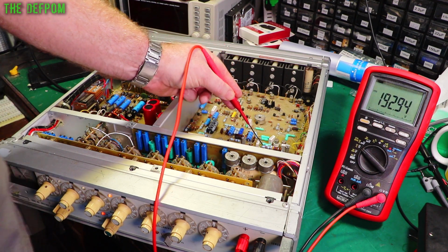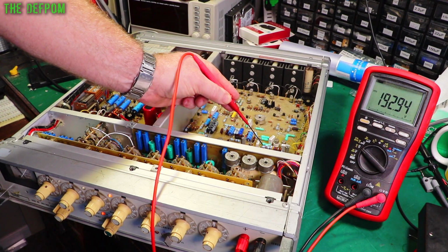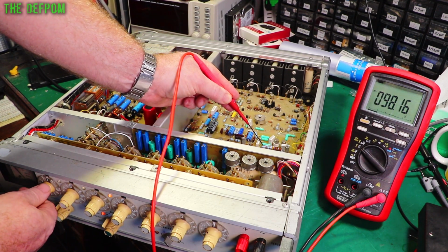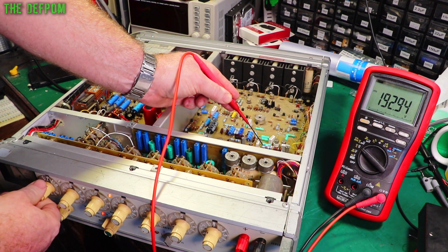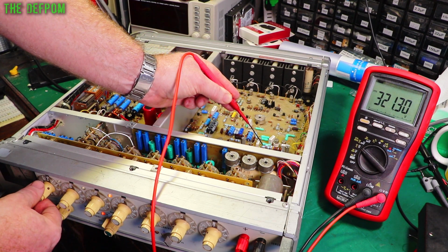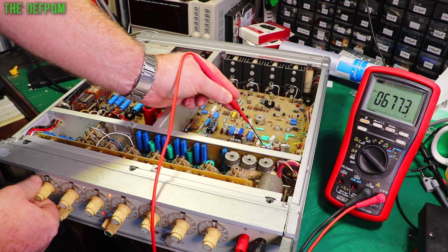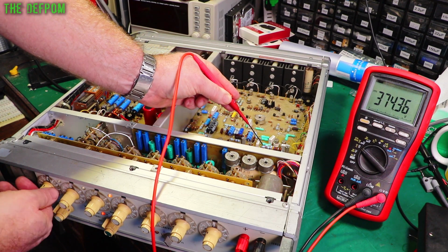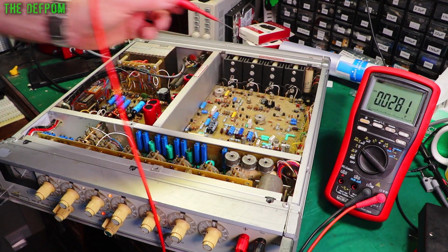So let's stick a probe on there. I'm currently set at 200 volts. Let's get 192. Go to 100, 98. So it's like 2 volts down, 7 volts down. So that's 300 volts. 321. Okay, so that's definitely wrong. 400 volts, that's down a bit. 25 volts down. 500 volts, 600, and so on. That's 900, that's 1000. This is relative to the negative output terminal. So this voltage here is wrong. And that's what's coming back from the divider network.